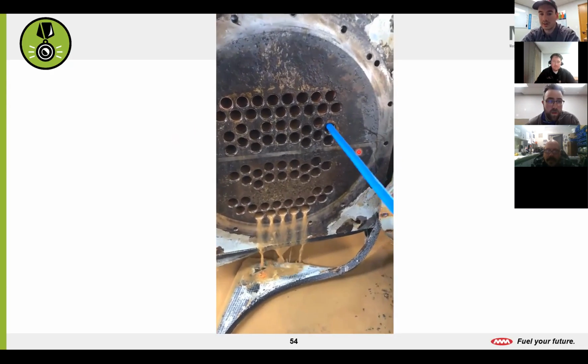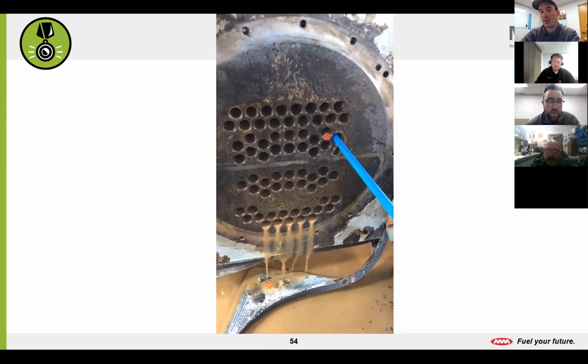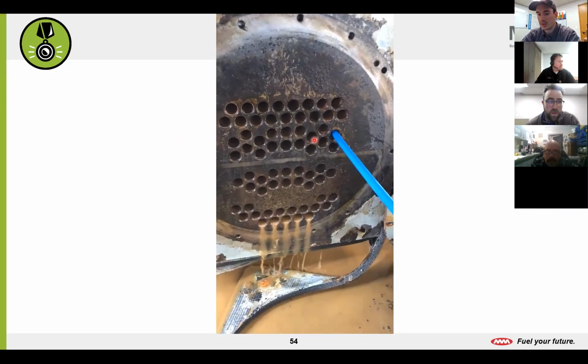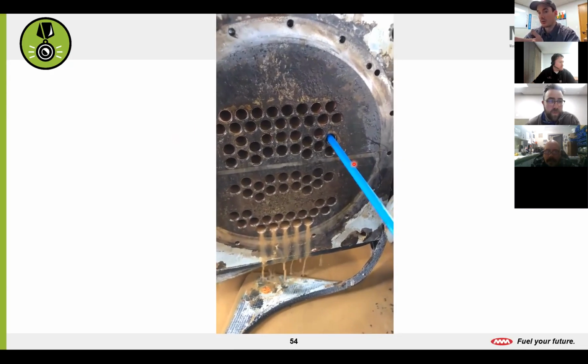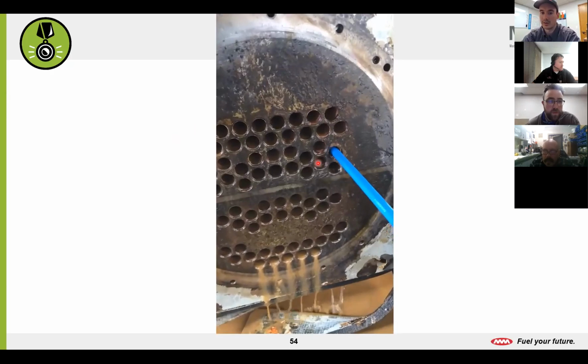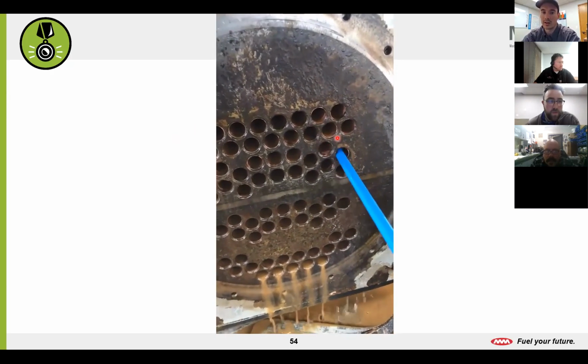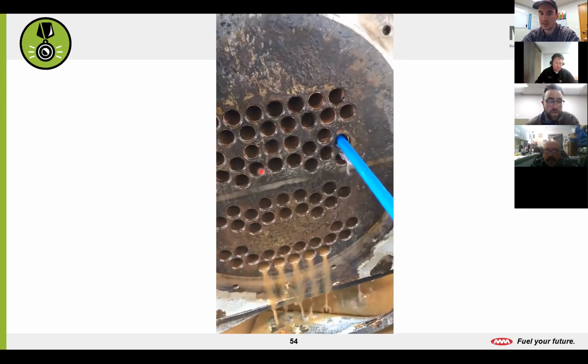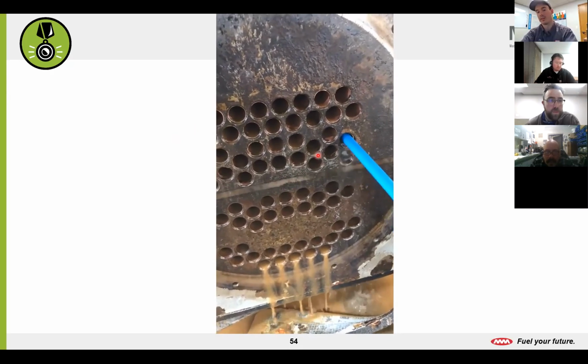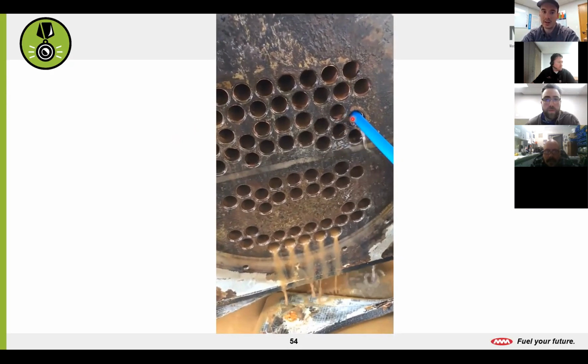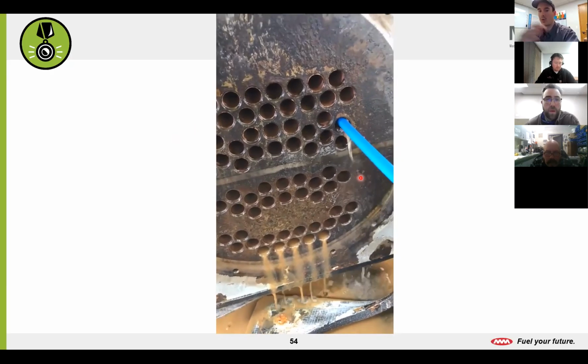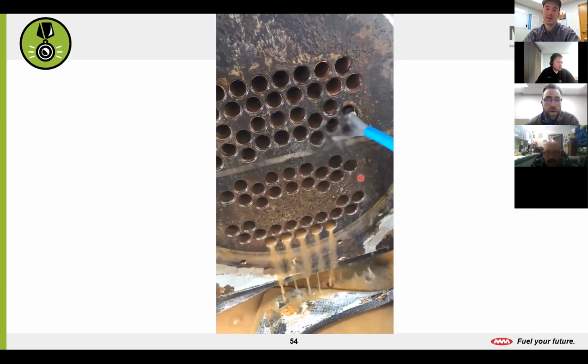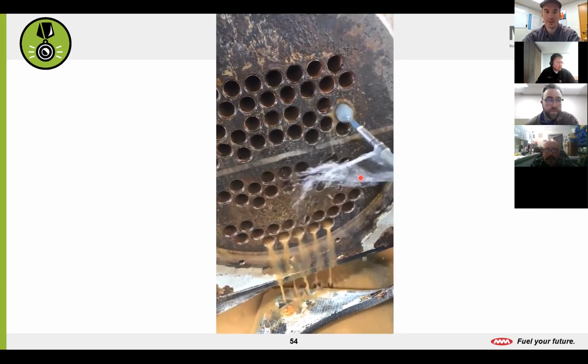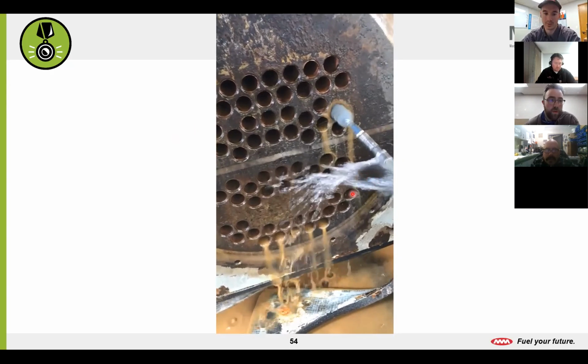But with water comes water treatment. And what we want to do is make sure that we don't have any dirt or grime or bio growth. If your chemicals are out of whack and you're getting stuff growing in there, you don't want that coating these tubes and basically acting as an insulator, because if it acts as an insulator, we can't transfer heat across it. We can't transfer heat from the water to the refrigerant. And then you'll lose huge efficiency. You'll have all kinds of efficiency problems. You'll have pressure problems. Your compressor will have issues. It's just a cascading effect. So it has to get done all the time.